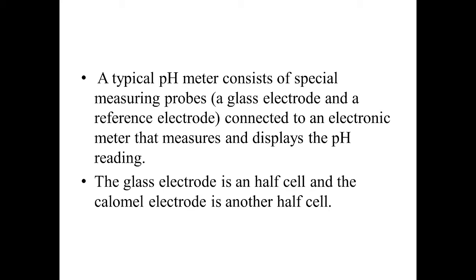A pH meter can be manual or digital. Nowadays, in most laboratories or research labs, we have digital pH meters. A typical pH meter consists of a special measuring probe. We call it the pH probe. That consists of a glass electrode and a reference electrode, which is a calomel electrode. These two are connected to an electronic meter. That electronic meter measures and displays the pH reading.